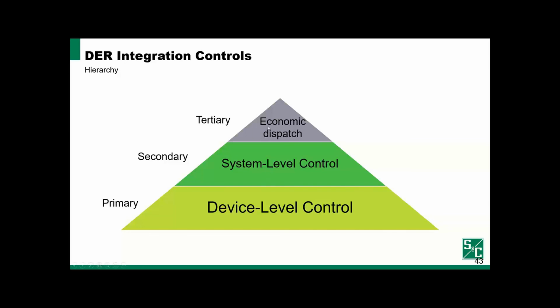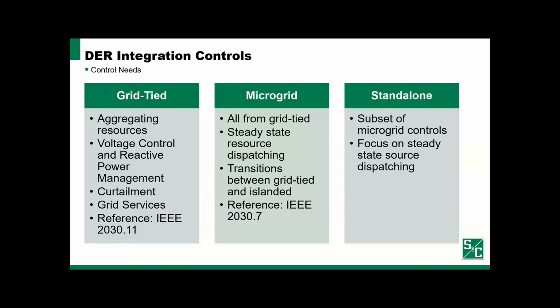Sitting above the secondary level is the tertiary control, which is typically responsible for slower considerations like economic dispatch, things that operate on the scale of minutes to decide what resources are most cost effective to operate at a given time. Like I said, this hierarchical approach can be applied to both DER penetrated systems as well as microgrid systems. Let's look at what's entailed in some of those different examples here.